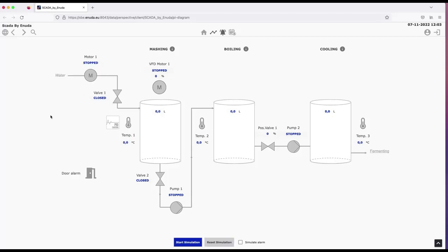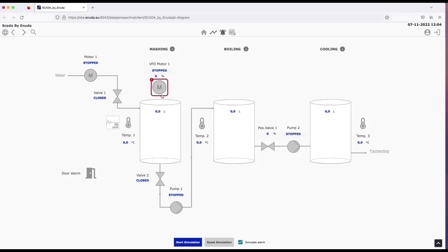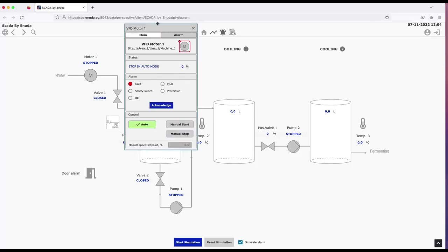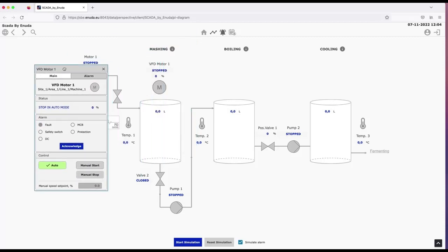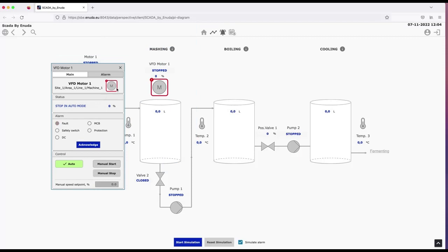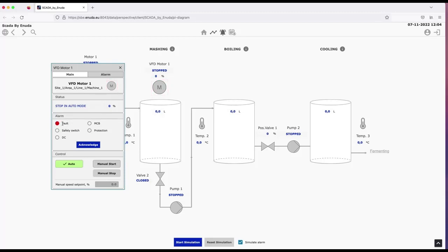So let's have a look at the alarming here. So we can simulate an alarm on one of the symbols here. So this motor is currently in alarm. So there is a frame around it and it's blinking, it's flashing because it's in alarm state. I could open the face plate again and we can see the same thing here that the symbol here is in alarm. We can even see down here in the alarm section what is the problem. I can acknowledge the alarm. Then it stops the blinking. But it's still there because the alarm is still active.